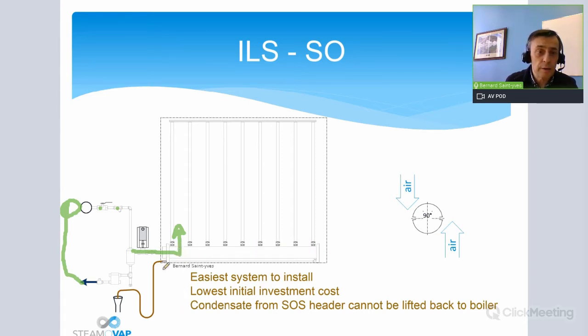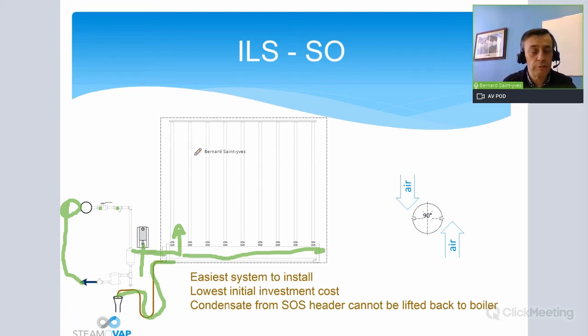The thing is, with this kind of system, everything after the valve has no pressure. So if there is no pressure after the valve, all the condensate accumulated here will not be able to go back to the boiler, which is considered a loss. You can imagine that if you have a lot of tubes, a lot of vertical manifolds, in an air duct at 55 Fahrenheit, 12 degrees Celsius, you will have a heat exchange between the two. The hot pipe here will create a lot of condensate going to the drain.